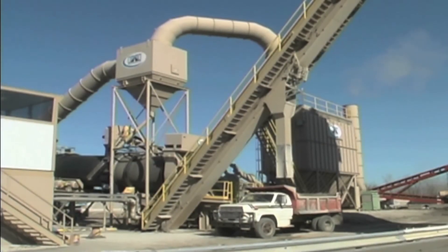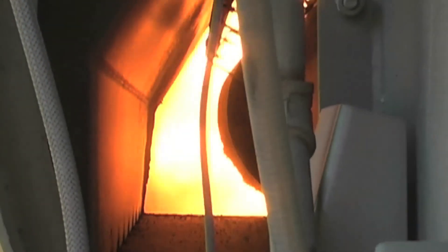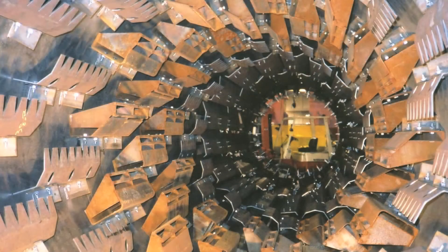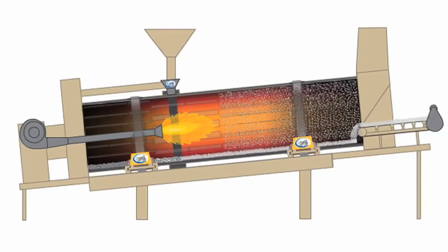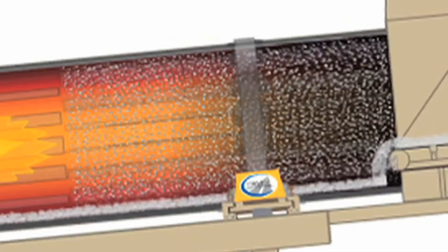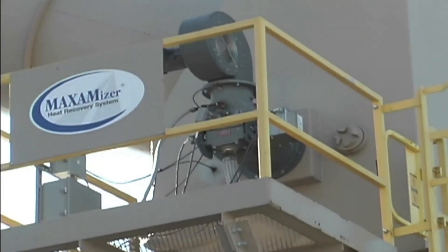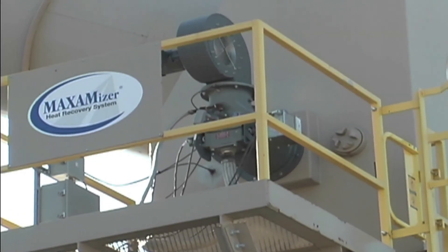MAXAMizer enables you to direct more of your fuel to heating product inside the drum instead of heating air inside the bag house. Flighting is set up to create a heavy veil that captures more of the main burner heat in aggregate. A smaller modulating heater is dedicated solely to maintaining bag house temperature.